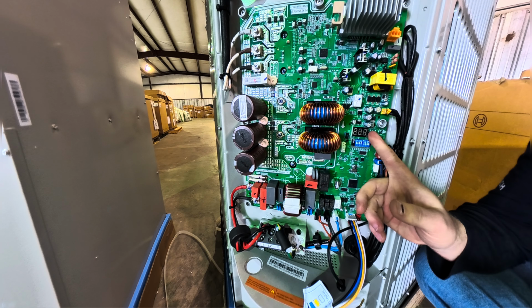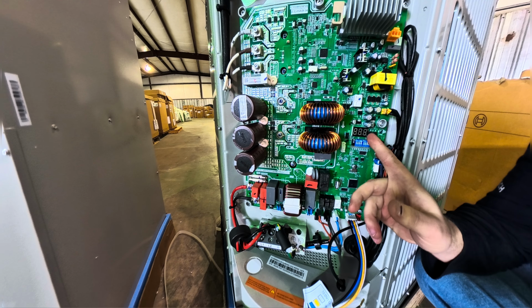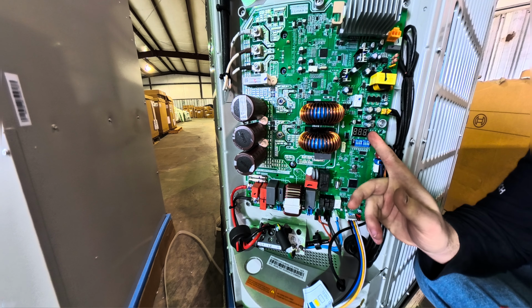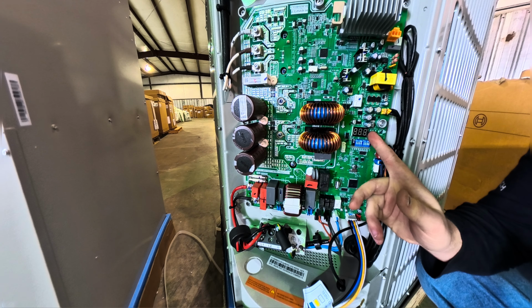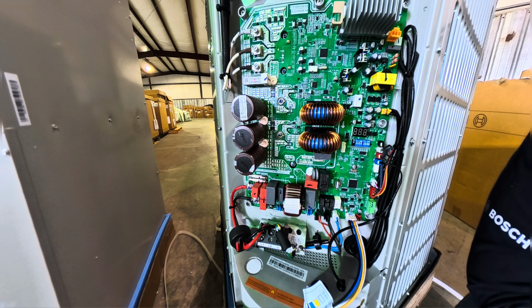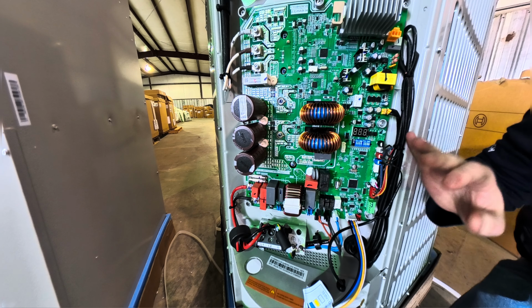It has a check parameters button. There's your screen. It has a check button right next to that screen. So you can go through your parameters. There is 31 of them. You can see what it's set up as. It would say H5 if it's a 5-ton heat pump, or H4 if it's a 4-ton heat pump, and so forth. It's going to tell you system codes. It's going to tell you if you have a call for cooling or heating. It's going to tell you all your temperature sensors.